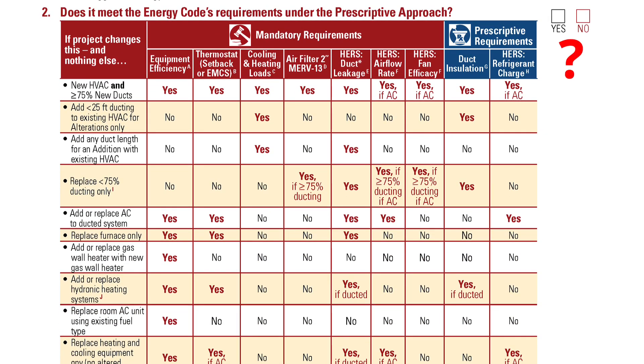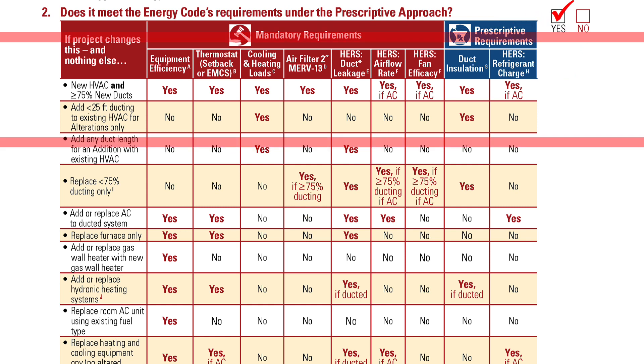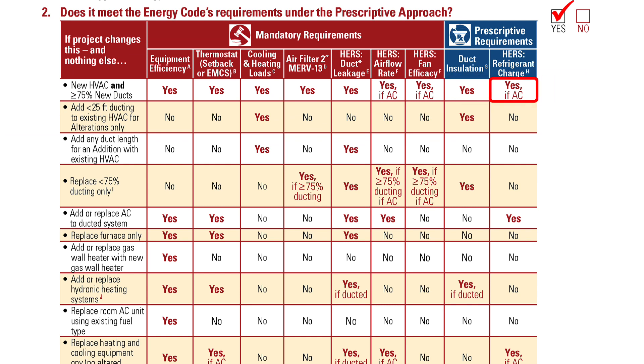Does it meet the energy code's requirements under the prescriptive approach? Yes, according to the table, a project that has a new heating, ventilation, and air conditioning system and greater than or equal to 75% new ducts can use the prescriptive approach. Be aware, though, that a footnote is also cited for this scenario in the table, which likely means some additional requirements apply.